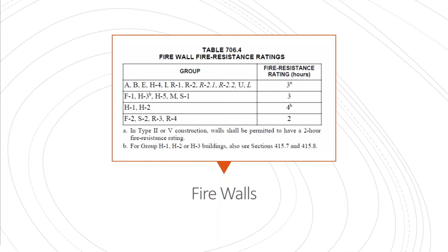You'll see up top is where the I group, I occupancy, is, and that indicates that the 3-hour rating is required between those occupancies that are adjacent to the I. And then footnote A, always remember the footnotes. Footnote A says in type 2 or 5 construction, walls shall be permitted to have a 2-hour fire resistance rating. So not between type 2 and 5 construction, but if you have buildings with type 2 and if you have buildings with type 5, you can reduce it.